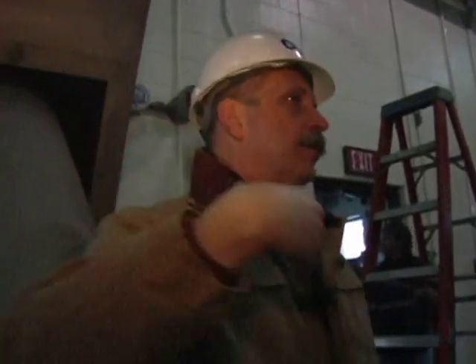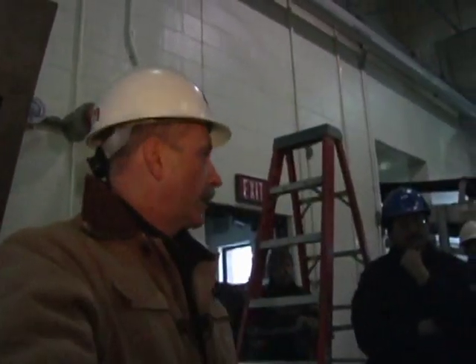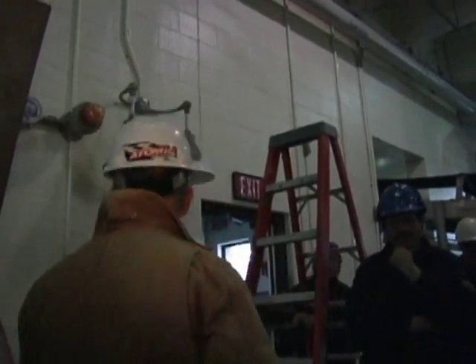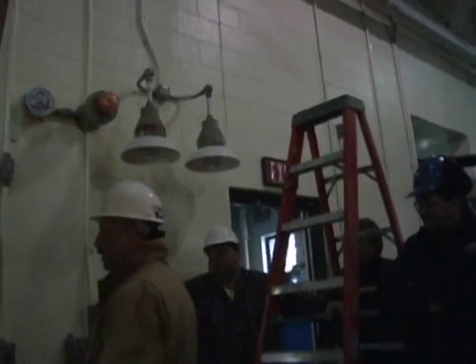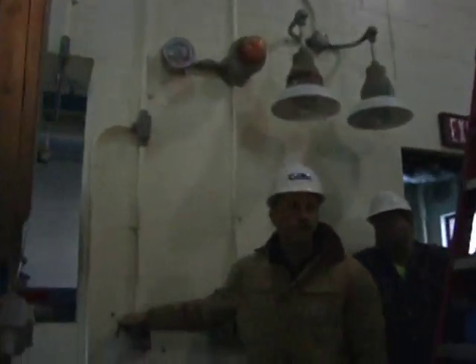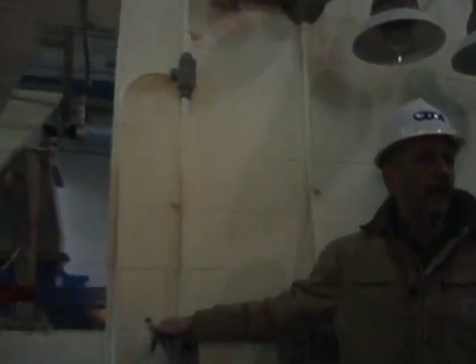When you go to automatic in this location, that transfers control to the control panel itself within the electrical room, and we'll take a look at that in a few minutes. Okay? The screw conveyor, hand-off-auto switch here in order to run the piece of equipment. Running it in hand, you can operate it locally at any time. If you go to automatic, that then transfers control to the SCADA system, and there is no other control panel for the screw conveyor itself. It goes directly to SCADA.